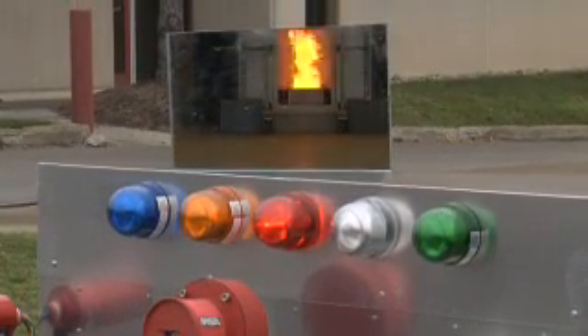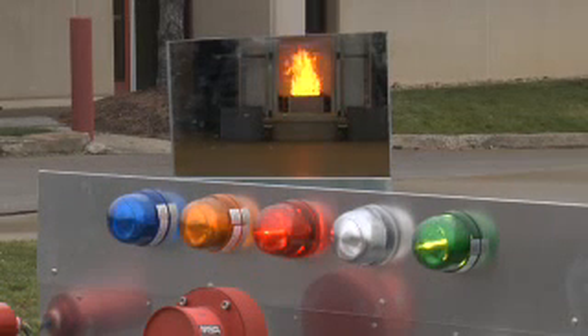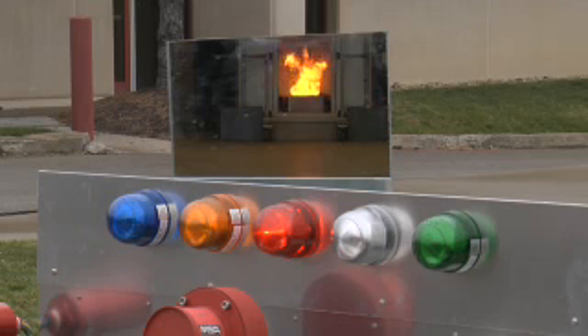As for the others, 18 seconds after the fire starts the Det-Tronics detector thinks it sees a fire but quickly changes its mind. The Fire Sentry and Spectrex units are simply not able to see a fire of this size at this distance.